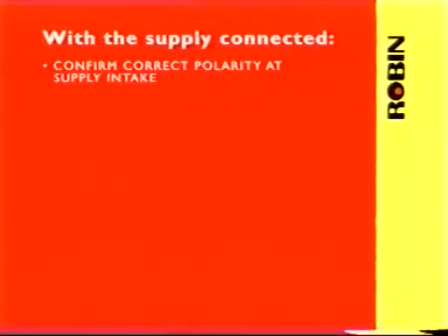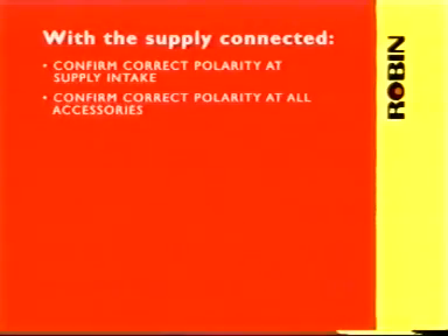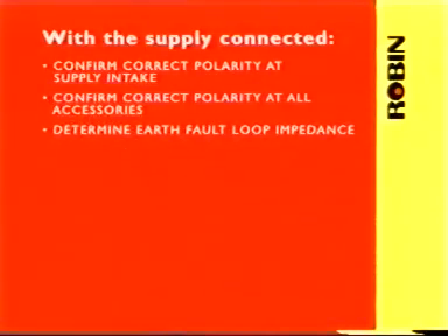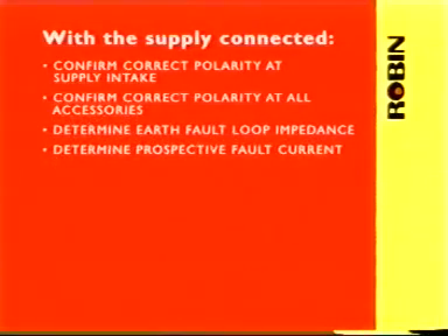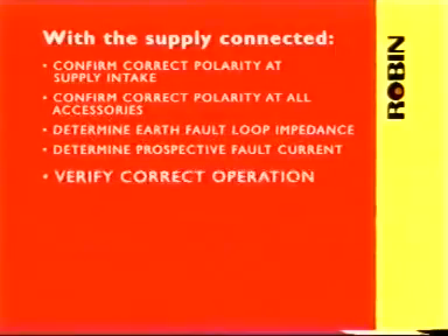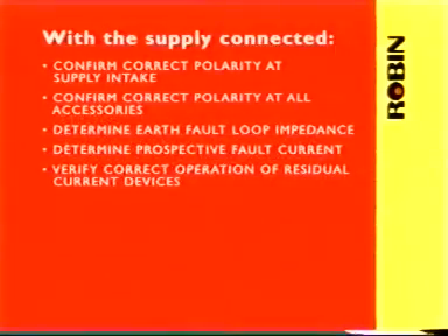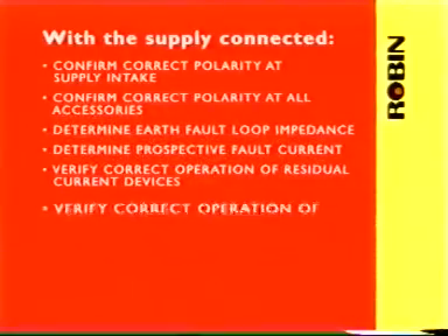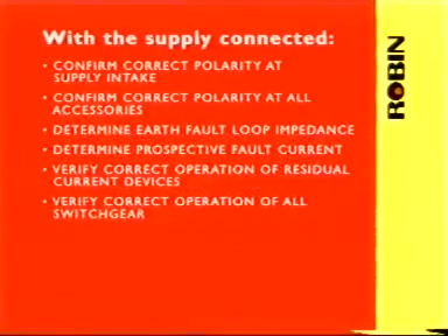Now, with a supply available, confirm correct polarity at supply intake. Confirm correct polarity at all accessories. Determine earth fault loop impedance at all outlets. Determine prospective fault current at all relevant points. Verify correct operation of residual current devices where fitted. Verify correct operation of switches, circuit breakers and isolators and all other switchgear.